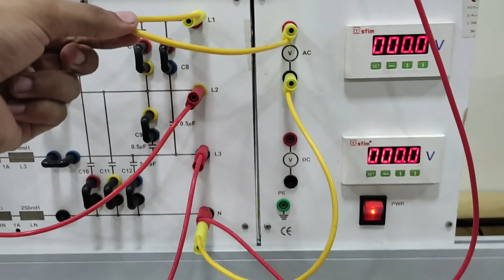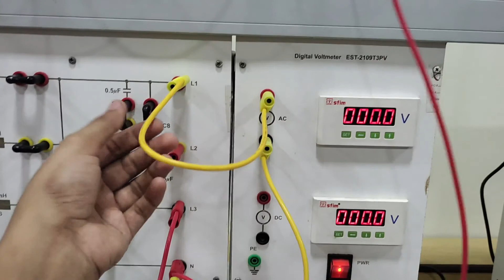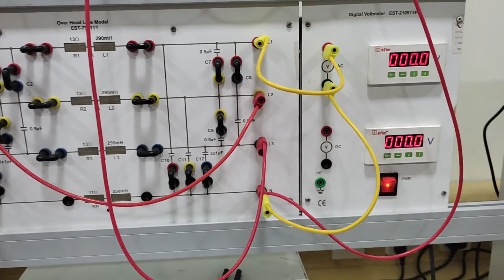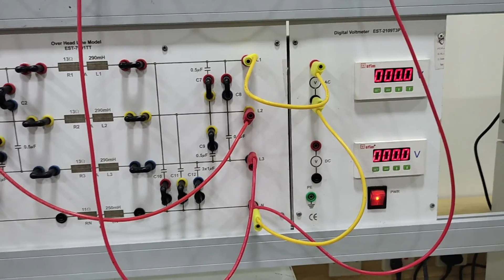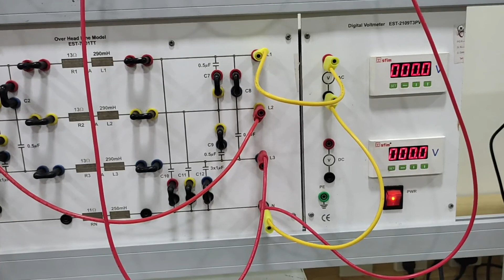Therefore we can measure the voltage for this phase L1. So we have connected a voltmeter in parallel. Here one wire goes towards the neutral and one goes towards the healthy phase L1. And students, as we have already seen in the previous task 1, the L1 phase was short circuited in the first task. So L1 current was there, but the voltage was 0 because it was short circuited. Therefore the short circuit voltage was 0. In this case L1 will have voltage because it is a healthy phase, and for L2 and L3 there is no need to measure the voltage because these are short circuited and their voltages will be 0, as we have already seen in task 1.